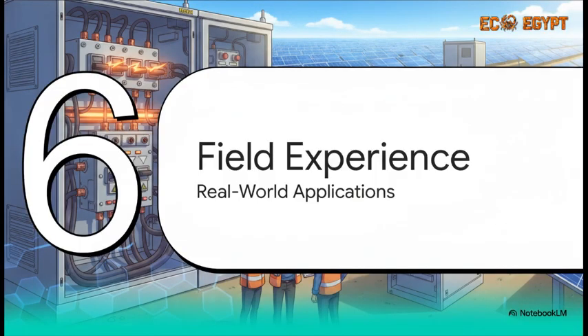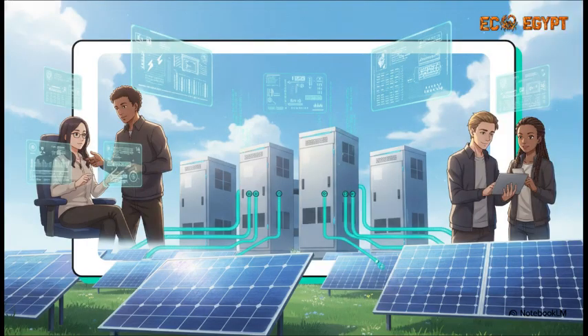And finally, Section 6, Real-World Field Experience. Engineering on paper is great, right? But operating a live, multi-million-dollar plant is a whole different ballgame. As MSc engineer Amer Awani notes from his direct experience managing a 60-megawatt PV plant, SCADA integration is an absolute game changer. By mapping the complete inputs and outputs of the switchgear directly to the SCADA system, a remote operator sitting miles and miles away can monitor breaker status, read electrical measurements, and clear protection trips. They get to do all of this safely without ever having to physically stand in front of a live, high-voltage panel.